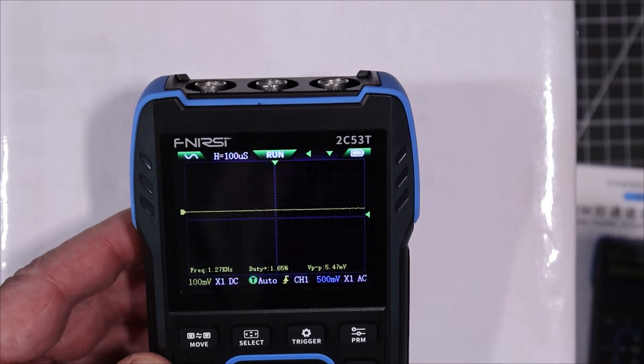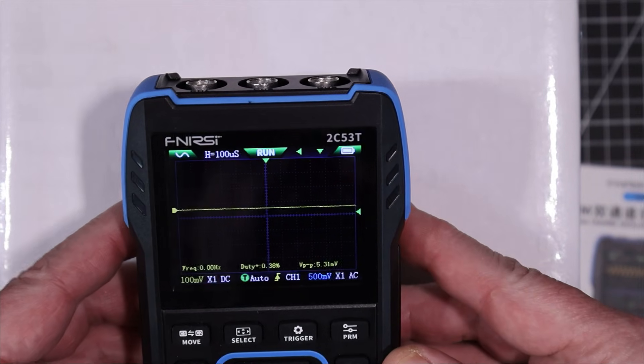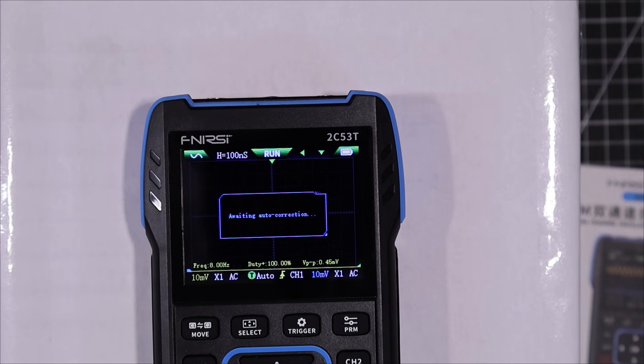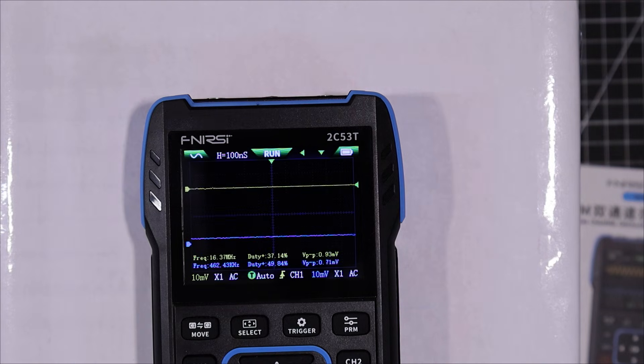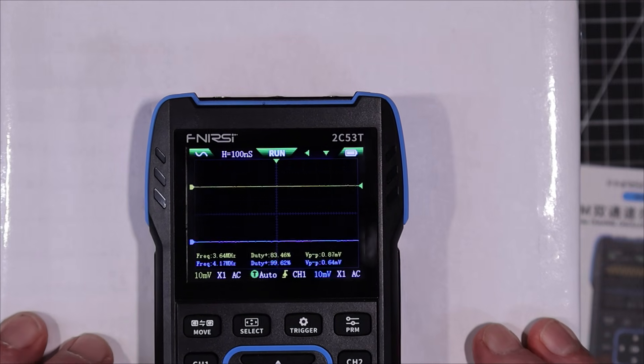As the manual says, the auto calibration does take a little while. You press the auto button and it goes through its process — that takes roughly two minutes to complete.